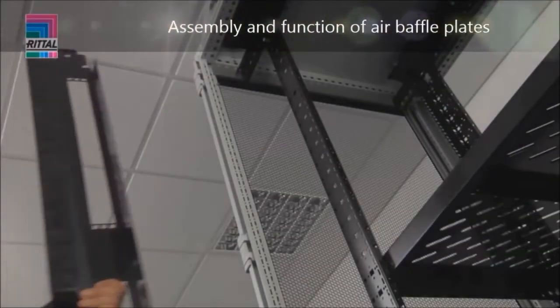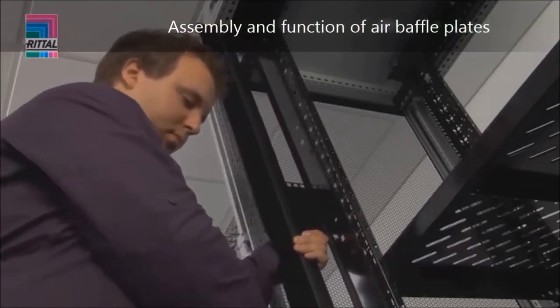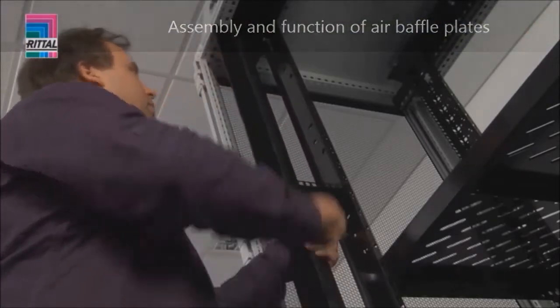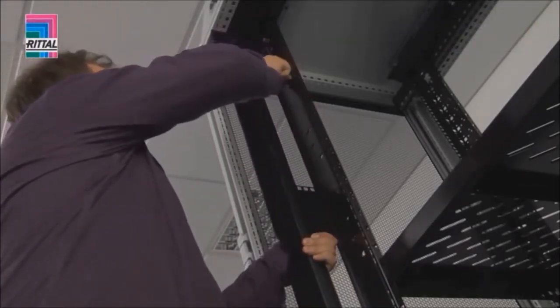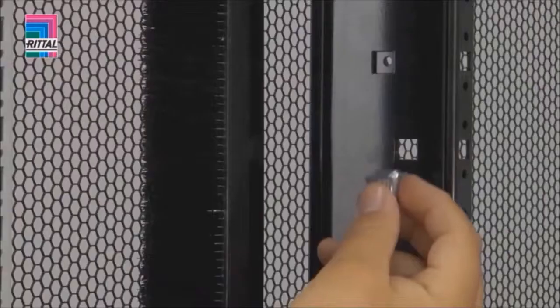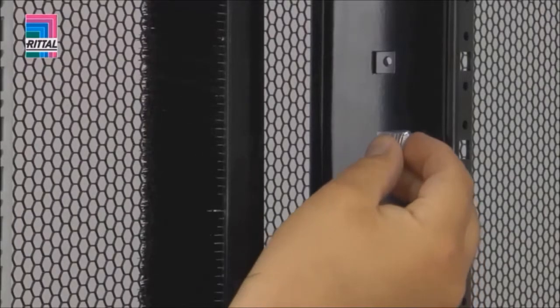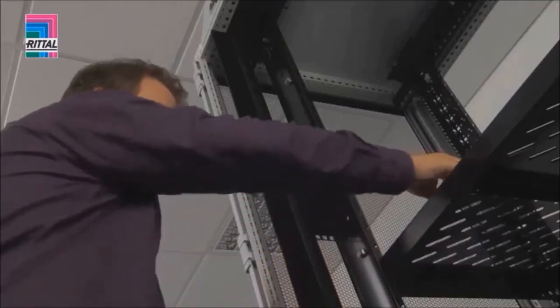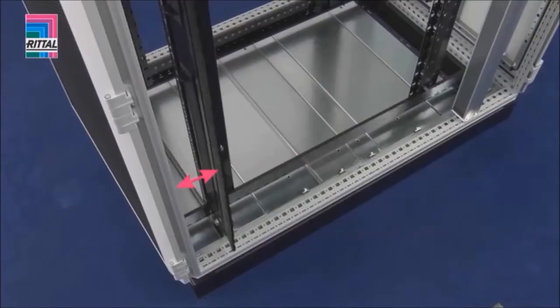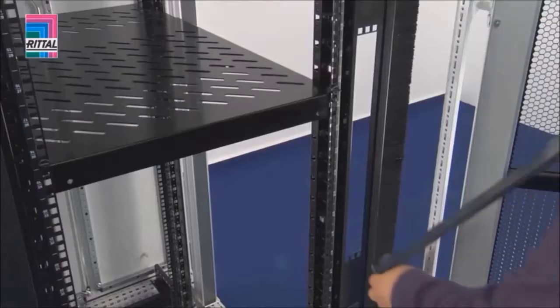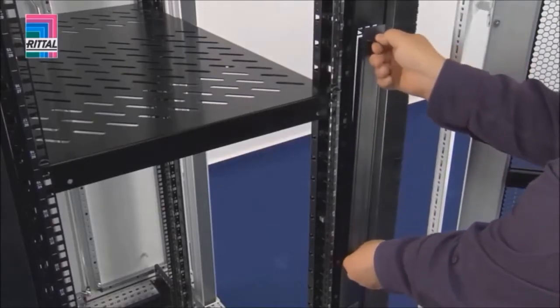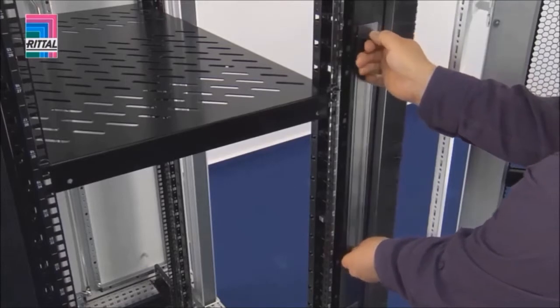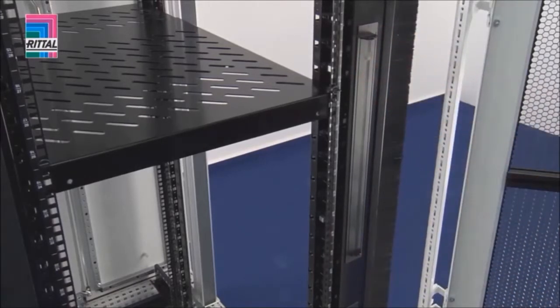The air baffle plates are used to separate the cold and hot zones inside the enclosure. They are secured using snap-in technology. For optimal air routing when using an LCP, the air baffle plates are simply rotated. Additional vertical height units in the air baffle plates provide extra assembly space.